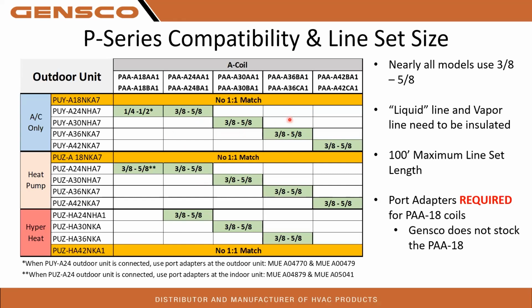For line set sizing, pretty much everything uses a 3/8, 5/8 line set, with the exception of this matchup right here. So a PUY 24 outdoor with a PAA 18 indoor coil is going to be a 1/4 by 1/2 line set. Notice there's a couple of asterisks next to those. If you come down here, you'll see you'll need port adapters for those on the 18 coil only.